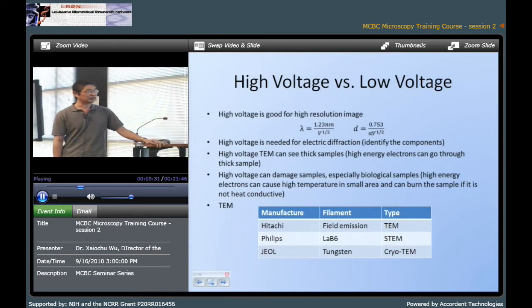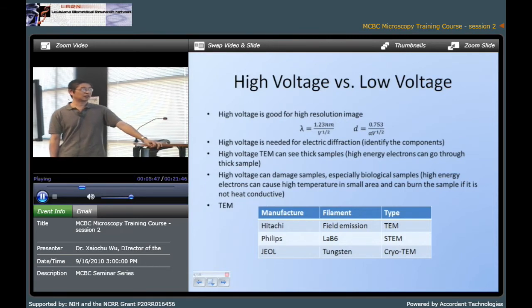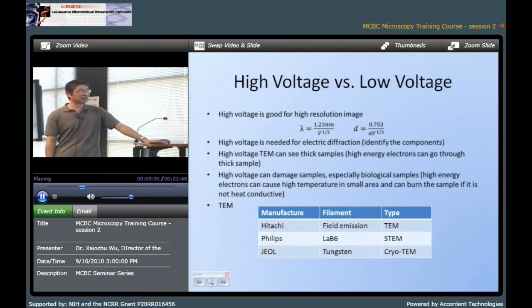The tungsten filament is comparably cheaper and very easy to maintain. Usually for regular biology research we prefer to use the tungsten filament. But if you want to see high resolution — especially if you want to see the atoms in your material — then you have to use LaB6 or field emission.